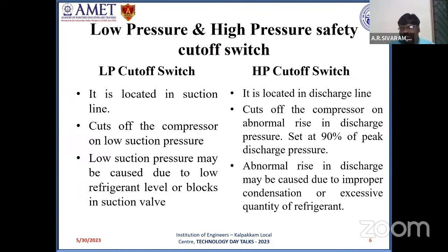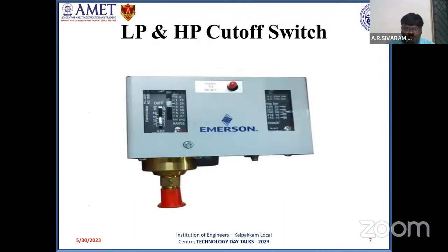That is, the HP cutoff switch, the high pressure safety cutoff switch, on an abnormal rise in discharge pressure will trip off the compressor. So improper working of the condenser is one reason for abnormal rise in discharge pressure, and excessive charging is another. That is, if the refrigerant is charged more than the required level, that could also result in an abnormal rise in discharge pressure. So these are the two switches: the LP switch, present at the compressor inlet, and the HP switch, present at the compressor outlet. These are the LP cutoff switch, that is the low pressure safety cutoff switch, and the high pressure safety cutoff switch.